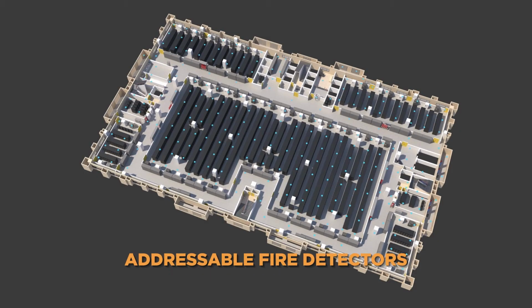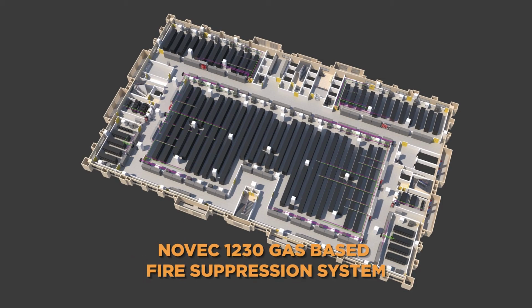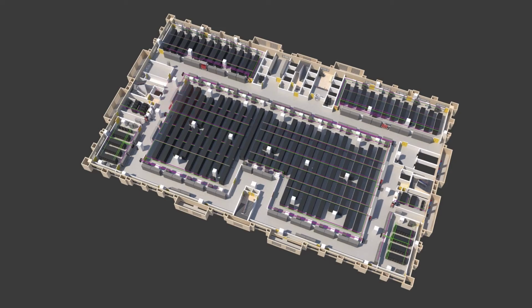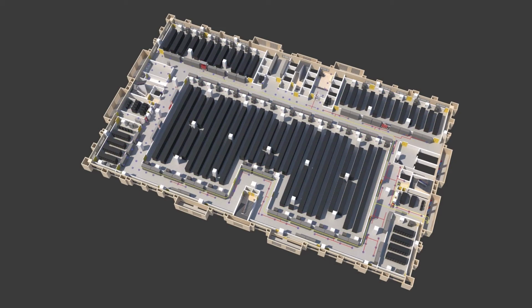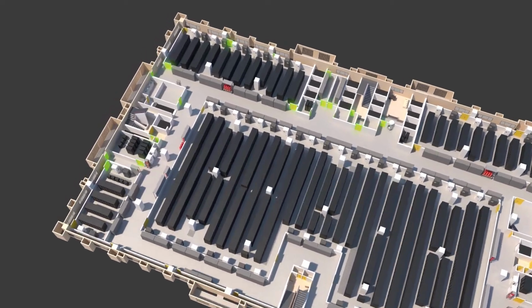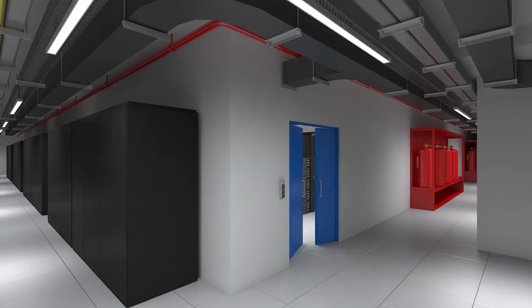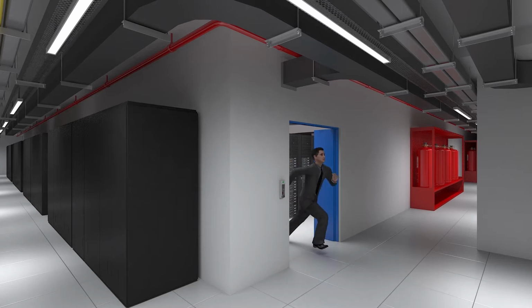Yotta NM1 is equipped with an addressable fire detection and suppression system that can intelligently detect the exact point of fire. The fire detection system is also integrated with our access control system. In case of a fire, the access control system automatically opens the doors of the affected adjacent areas for quick evacuation.